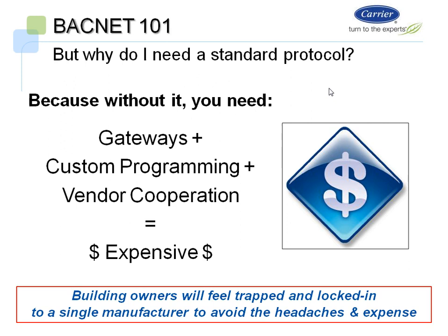If you do not have a standard protocol, it's still possible to integrate multiple pieces of equipment into one control system. However, it gets expensive and complicated. Generally you'd need some sort of gateway or translator that can integrate, for instance, Modbus to BACnet or LON to BACnet, or some communication between two protocols, which is generally expensive.